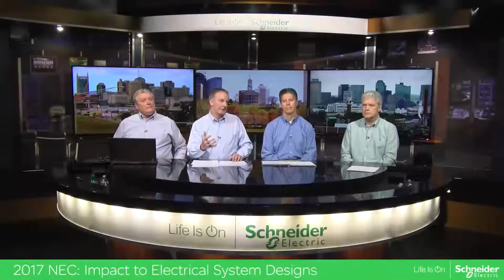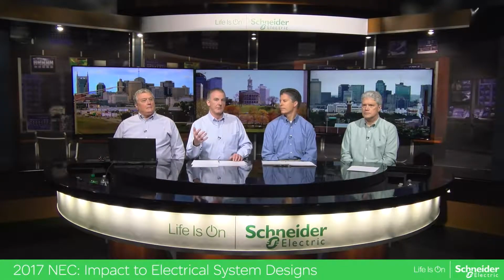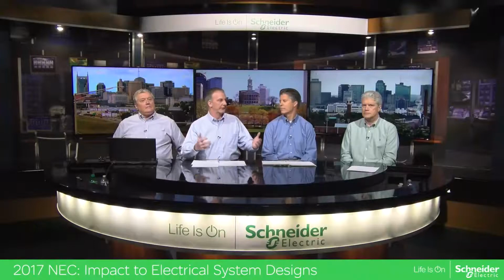220 is our area of the code where we do electrical calculations, right? So we run the calculations in accordance with 220. 220.12 specifically addresses the lighting requirements in the building. As we look at the table, you look at the occupancy, and you calculate your lighting loads based on a VA per square foot. That could be 2.5, 3.5, whatever the number is that's been established for the right lighting load in that building.